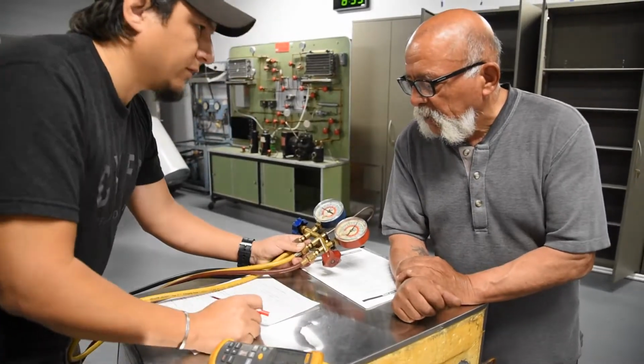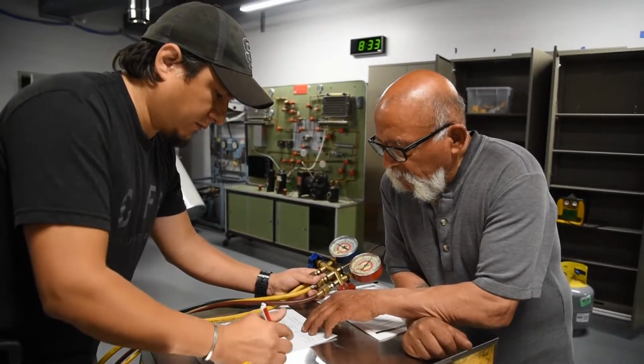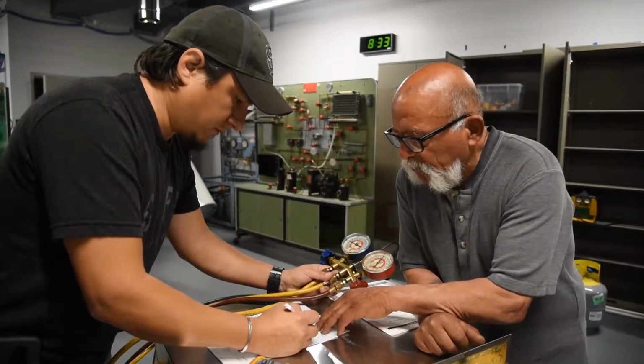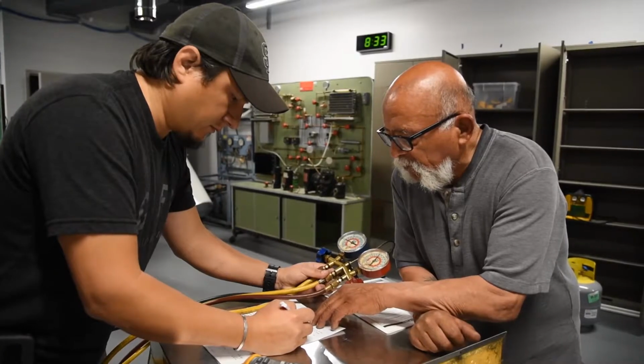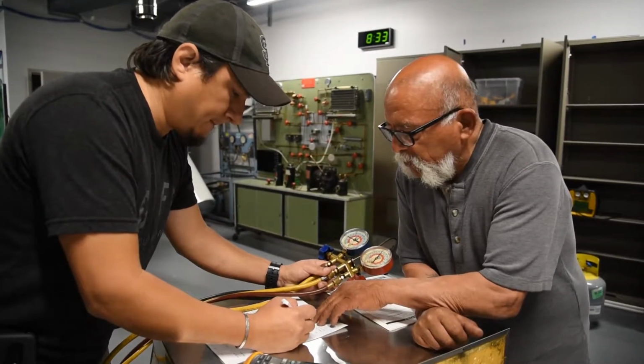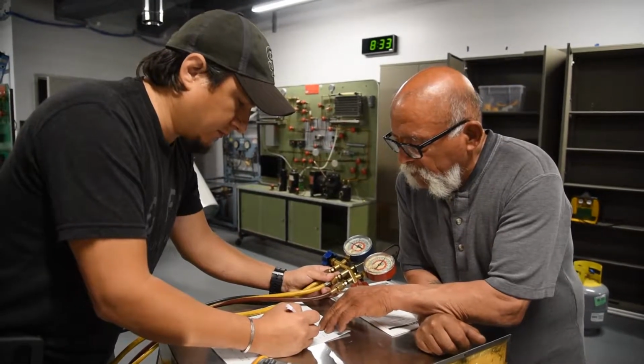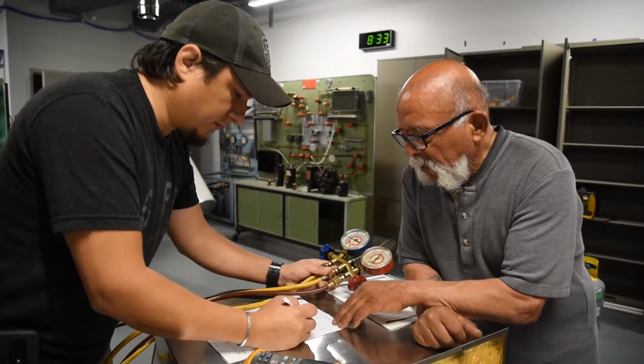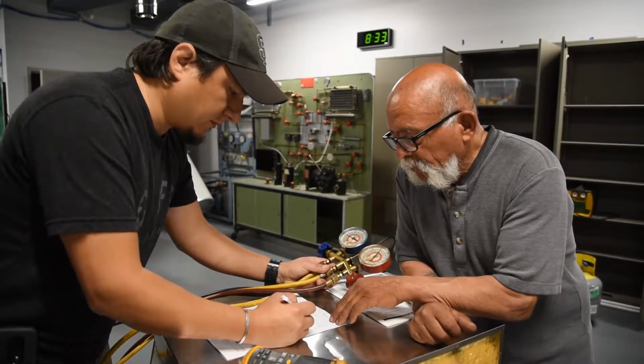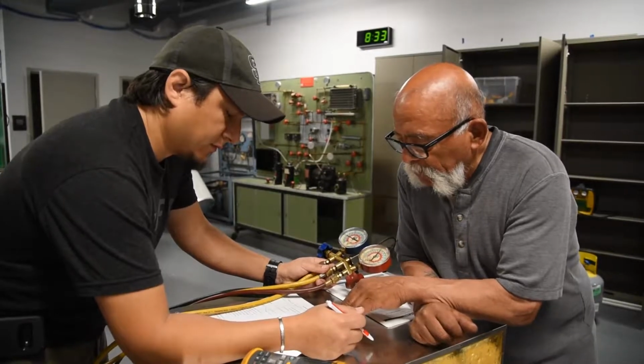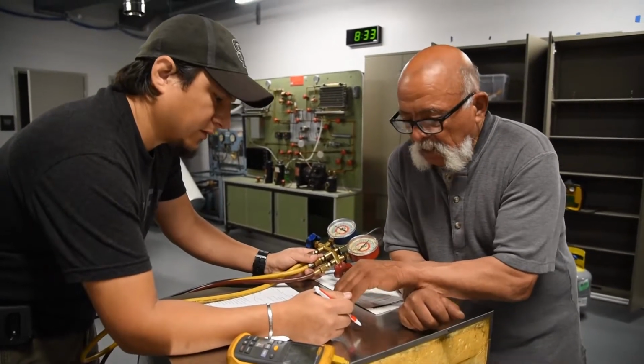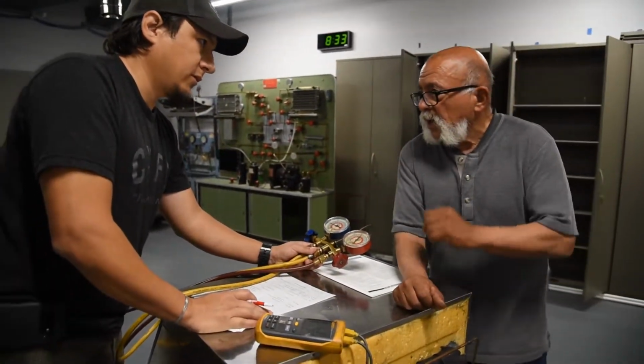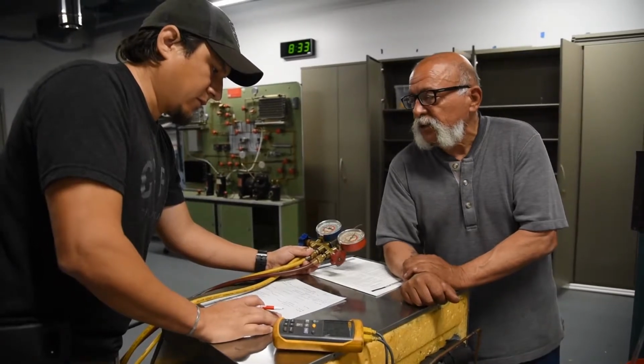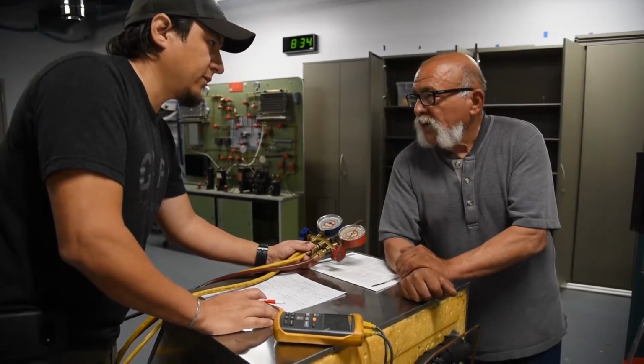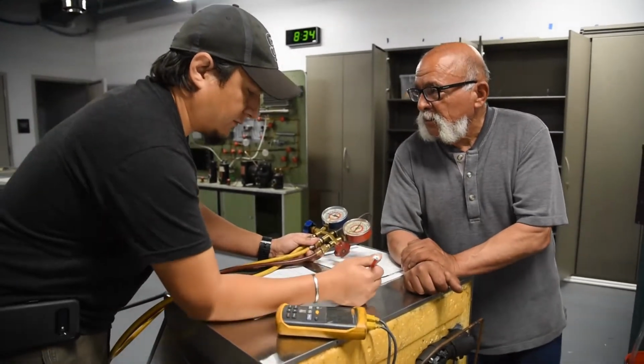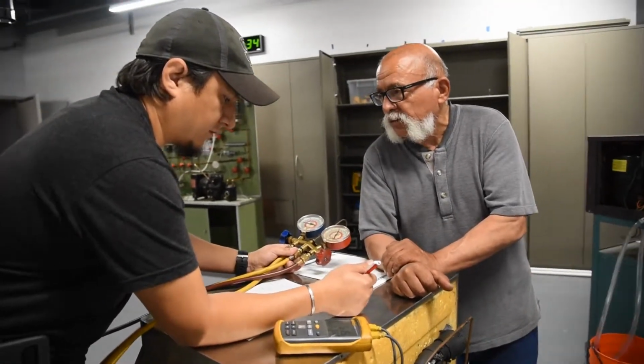Okay. So now we went from 0 psi to -10. It went into harvest. This is the low side, and it went up to 65 psi, 25 temperature. Right. Now what we have is it's going back into ice making. The low side is 50 psi and 15 degrees. Right. So what's starting to happen at 15 degrees? We're going down to start making ice. Why? Because it's below 32 degrees. Oh, below freezing point. Okay.